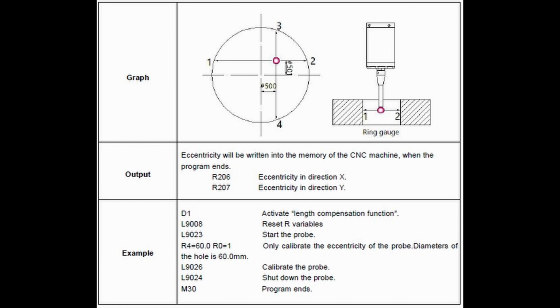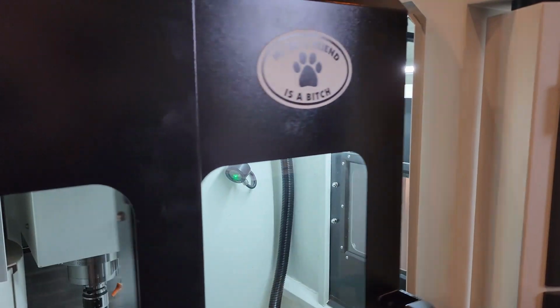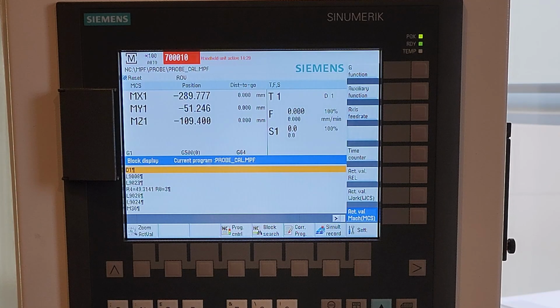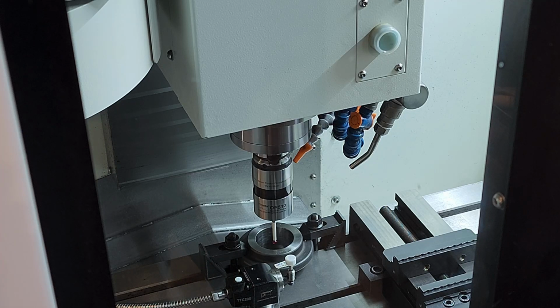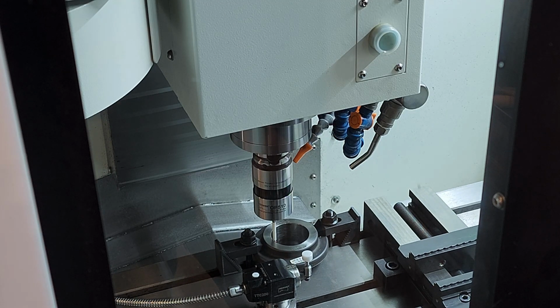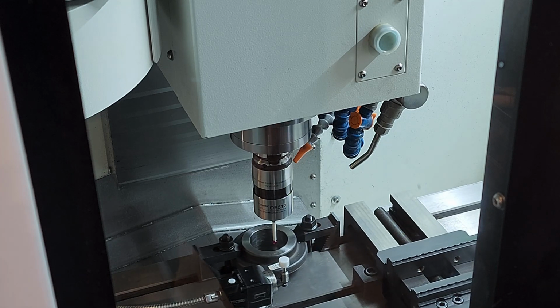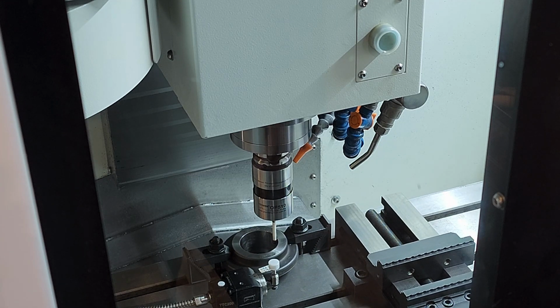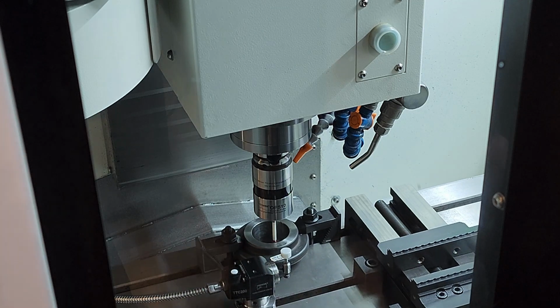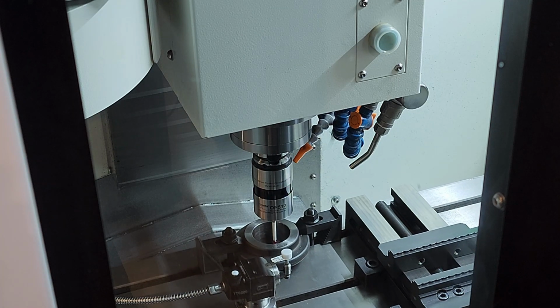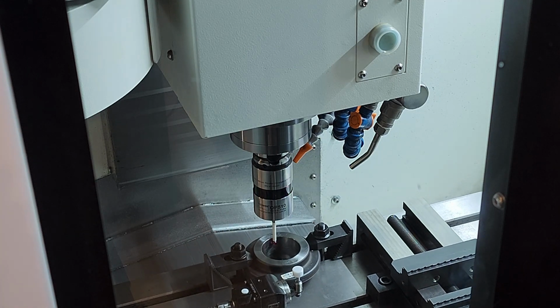To run the calibration program, shut the door, select the soft key next to the execute, and hit cycle start. The Ruby will contact and probe the ring gauge in the X and Y quadrants several times, and the variables for the eccentricity and the radius will be saved in R206 through R209 respectively.